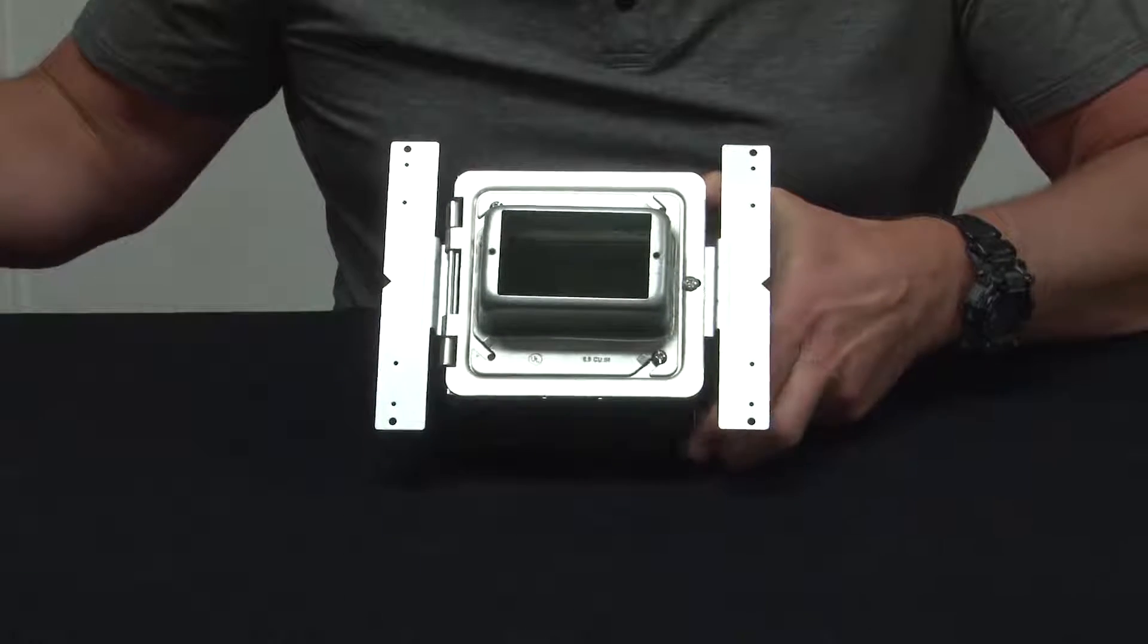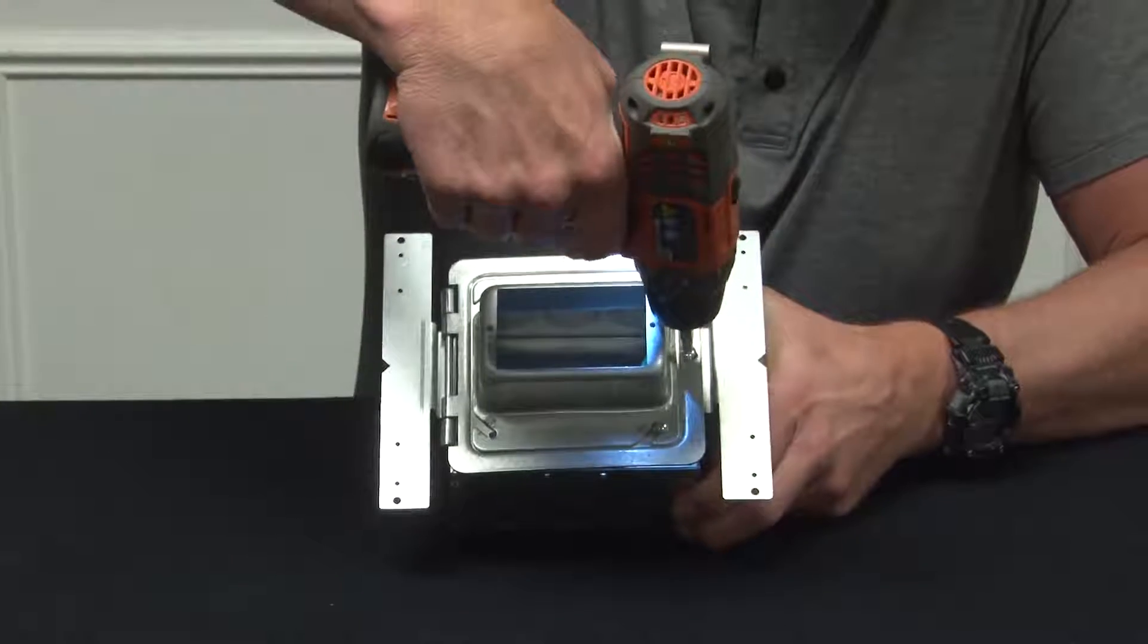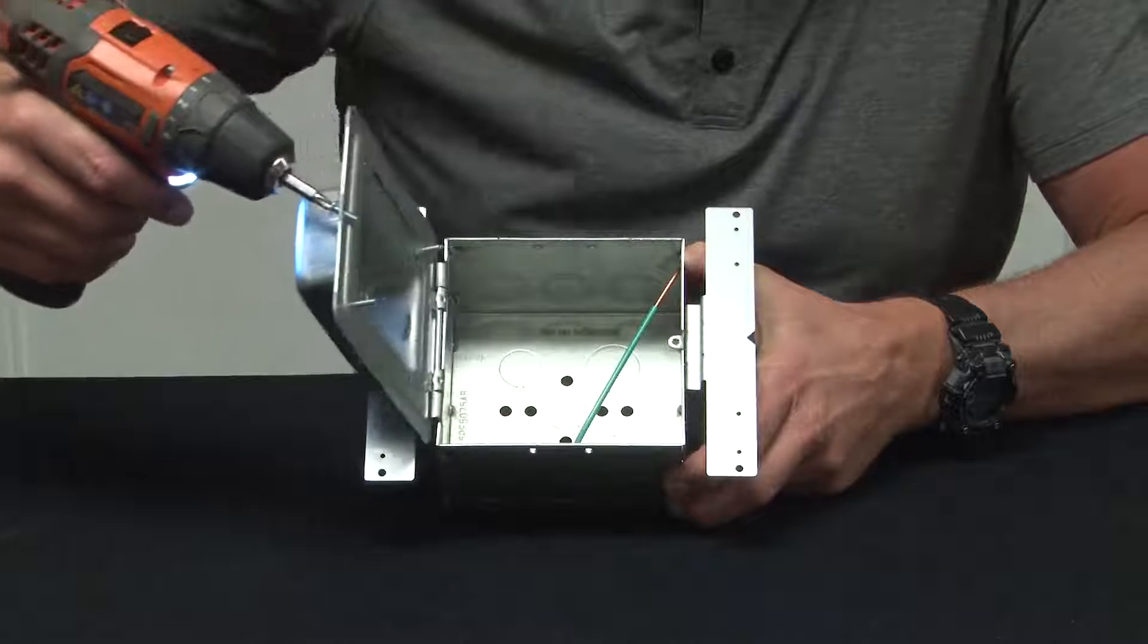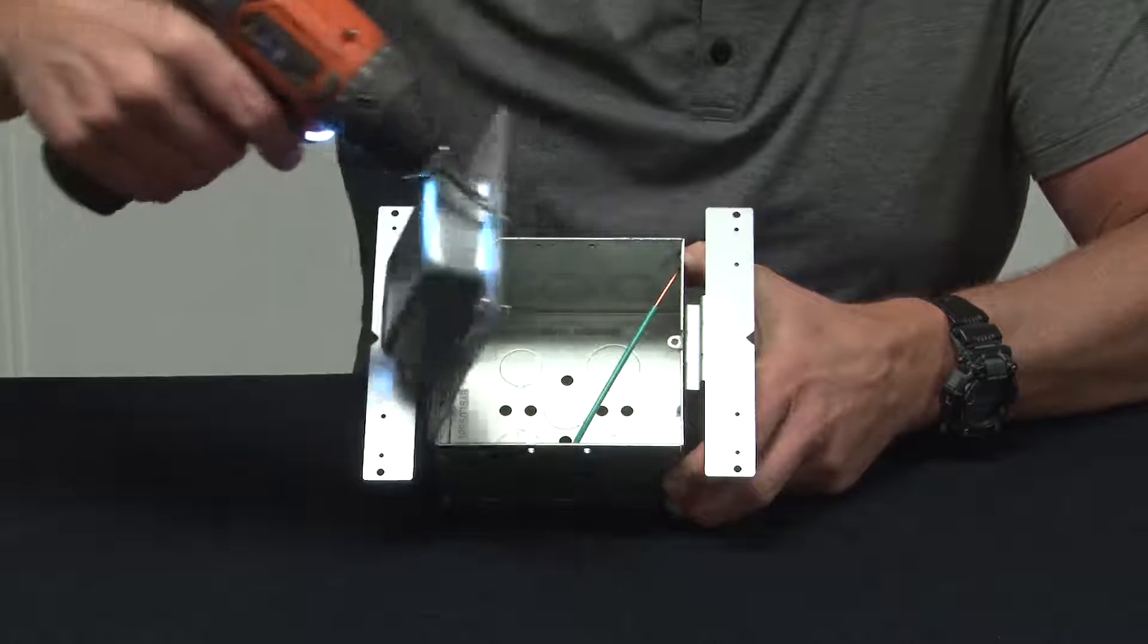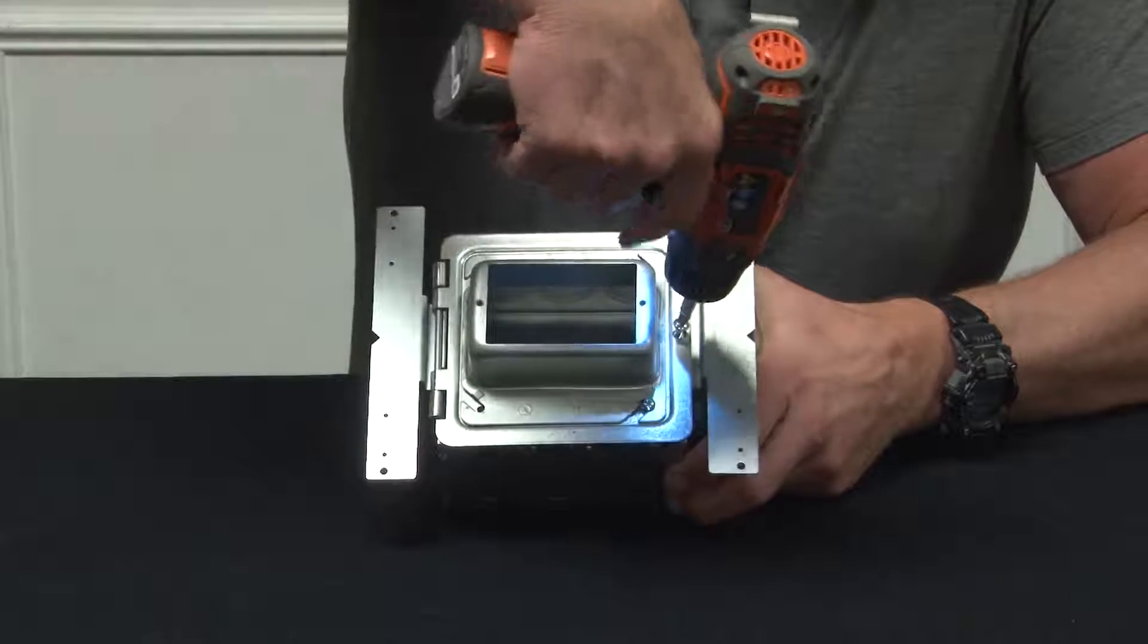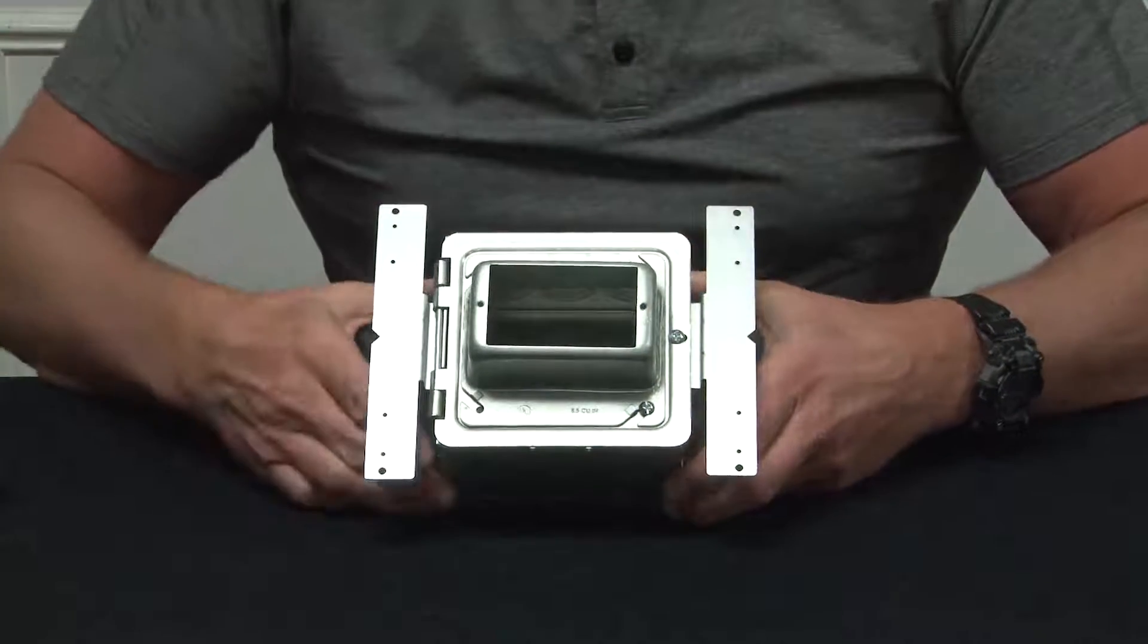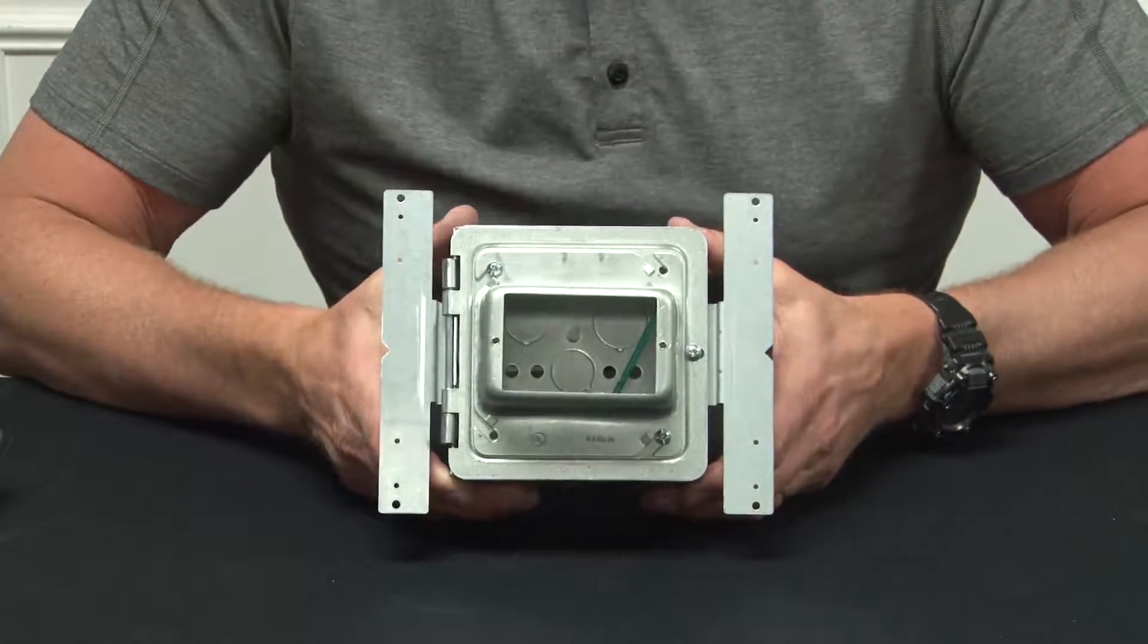What's unique about this box is it allows the installer to prefabricate: open the door, install the device with flying leads, put it back on the box, and close the door. So when you get to the job site, you simply mount it to the stud, open the door, and terminate the device.